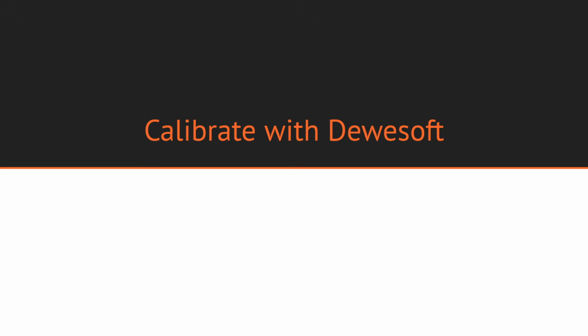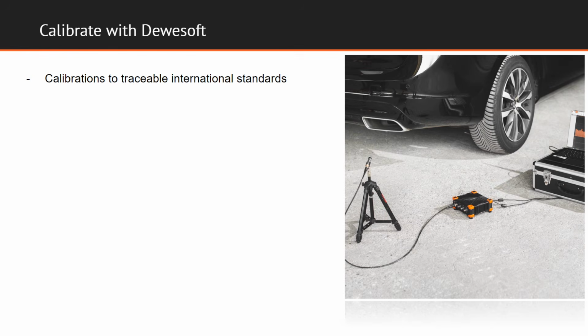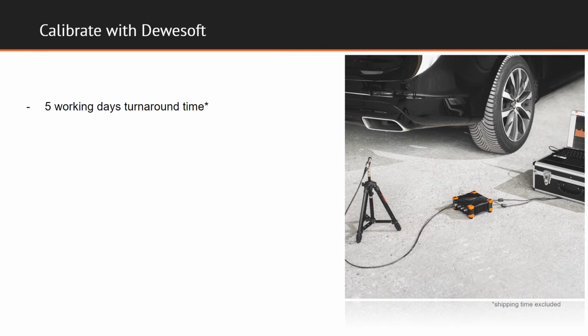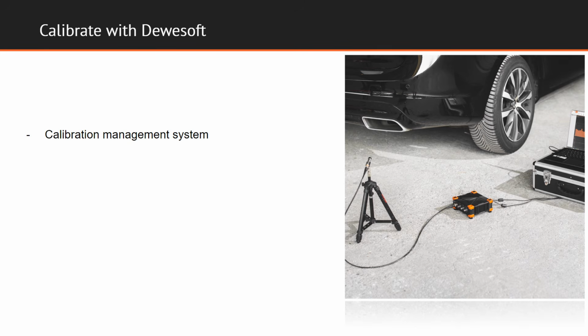In order to achieve this, we paid special attention to our customer needs when shaping our calibration services. To ensure the best possible execution and worldwide standard compliance, we partnered up with an experienced, internationally accredited calibration laboratory. As a result of this partnership, we are able to provide a highly competitive service featuring worldwide valid calibrations to traceable international standards, 5 working days turnaround time, state-of-the-art calibration management system tailored to the user. This way the user gets notified when calibration is about to expire and calibration process can be tracked while being performed.